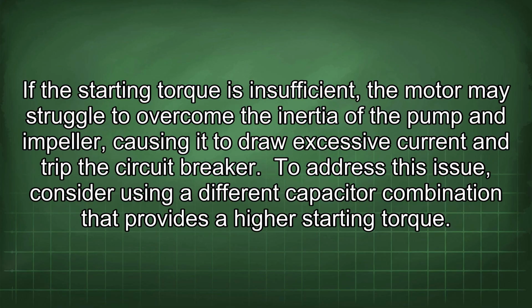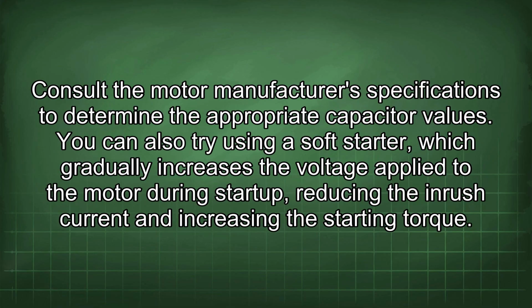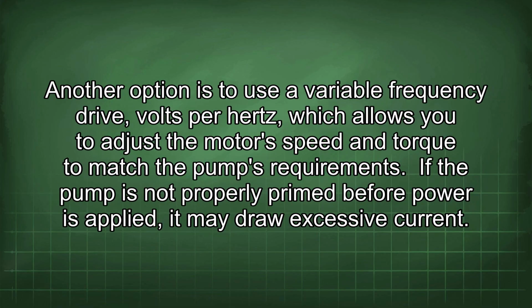To address this issue, consider using a different capacitor combination that provides a higher starting torque. Consult the motor manufacturer's specifications to determine the appropriate capacitor values. You can also try using a soft starter, which gradually increases the voltage applied to the motor during startup, reducing the inrush current and increasing the starting torque. Another option is to use a variable frequency drive, volts per hertz, which allows you to adjust the motor's speed and torque to match the pump's requirements.